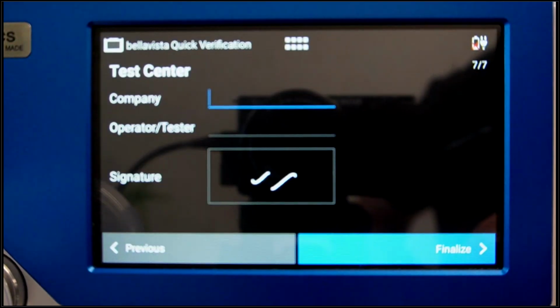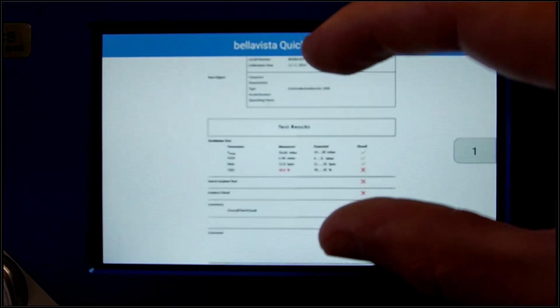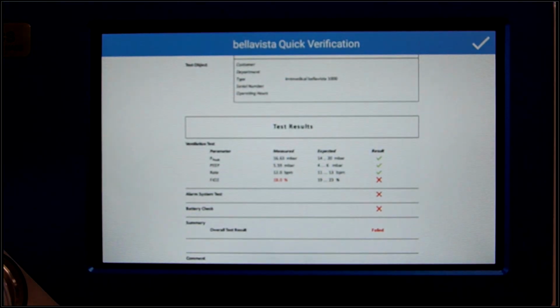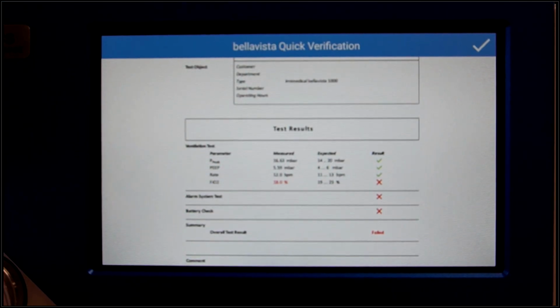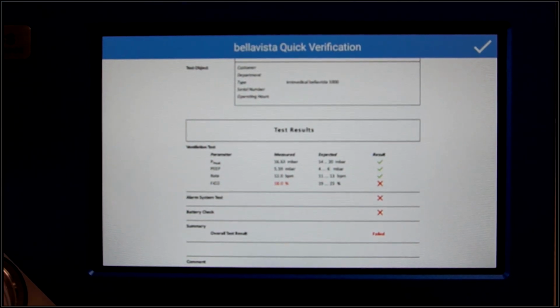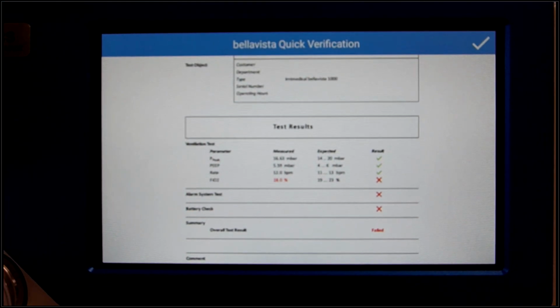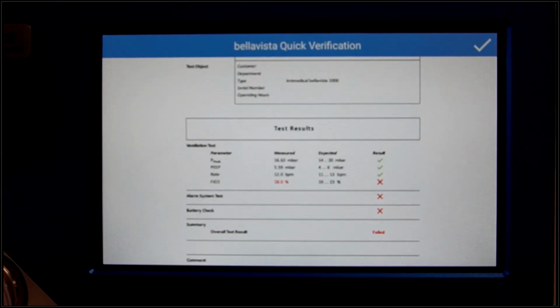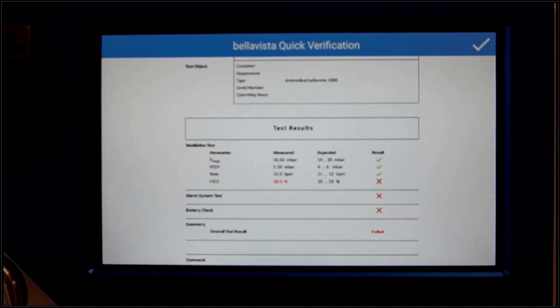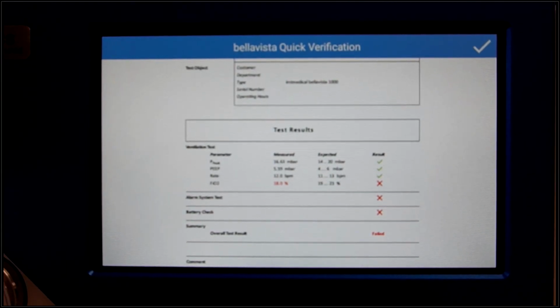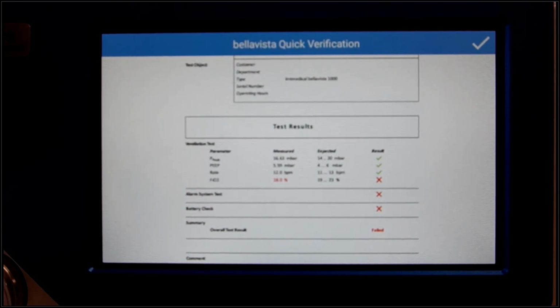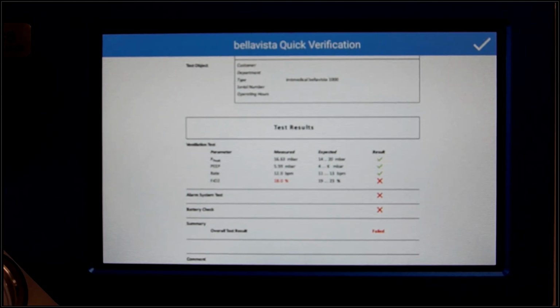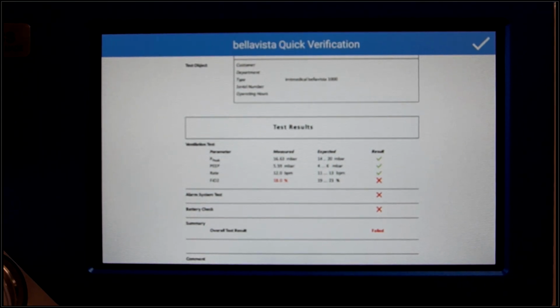And then that all goes into a report that you can download as a PDF file from the device. So as you can see, this actually makes testing workflows more efficient and it eliminates the risk of measurement and transcription errors, but it also ensures that your device is set up correctly, because things like gas type, gas standard, trigger settings are saved for that ventilator and are being loaded automatically when you start the app.